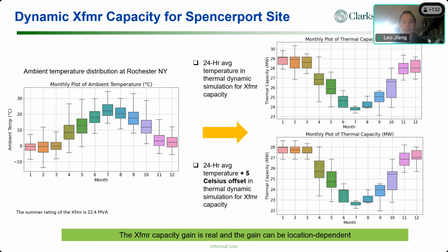Now we're using the historical data here, following the IEEE standard. We did both. In the upper right figure, we didn't apply the offset. What I mean is that we use the average temperature. We also increase the ambient temperature by 5 Celsius as an offset, trying to be more conservative. So those are the two scenarios, with results documented in the right side figures. If you have the 5 C offset temperature as a safety margin, your dynamic thermal capacity for the transformer will definitely be shifted lower. But regardless, if you look at the bottom right figure, the dynamic transformer rating will be much higher than the static 22.4 MVA for the site.